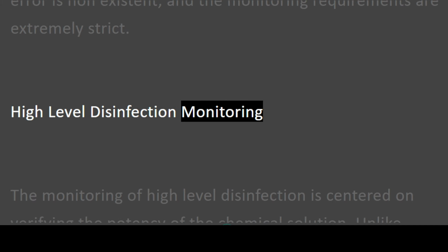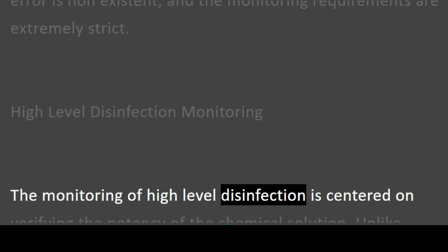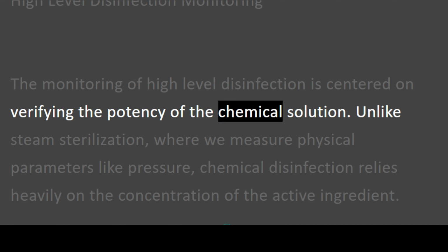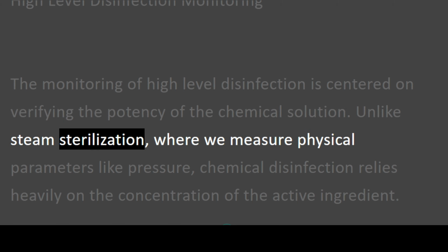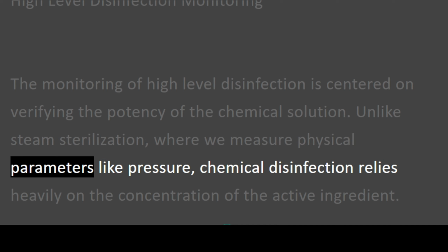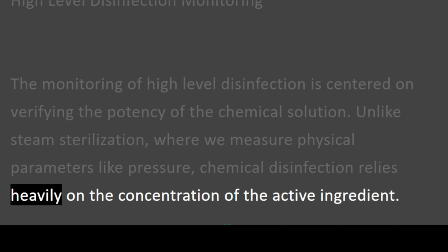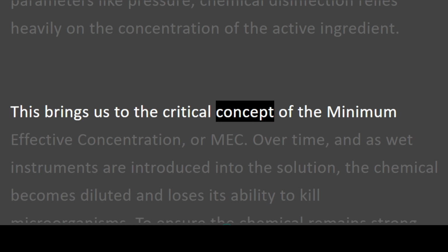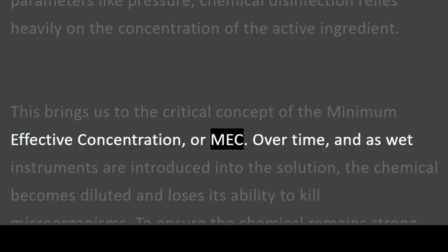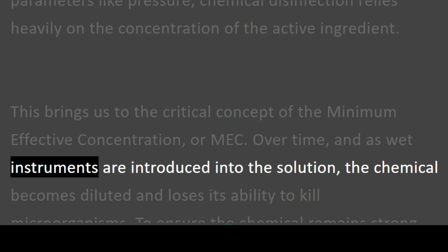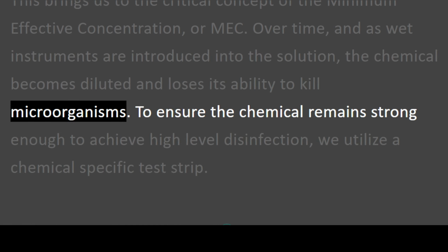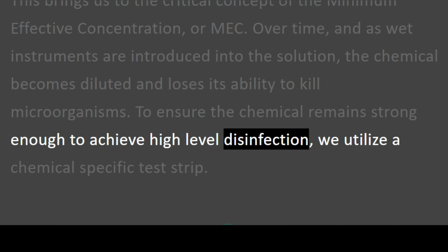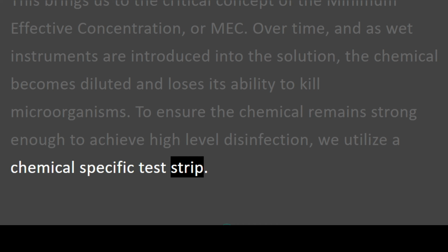High-level disinfection monitoring. The monitoring of high-level disinfection is centered on verifying the potency of the chemical solution. Unlike steam sterilization, where we measure physical parameters like pressure, chemical disinfection relies heavily on the concentration of the active ingredient. This brings us to the critical concept of the minimum effective concentration, or MEC. Over time, and as wet instruments are introduced into the solution, the chemical becomes diluted and loses its ability to kill microorganisms. To ensure the chemical remains strong enough to achieve high-level disinfection, we utilize a chemical-specific test strip.